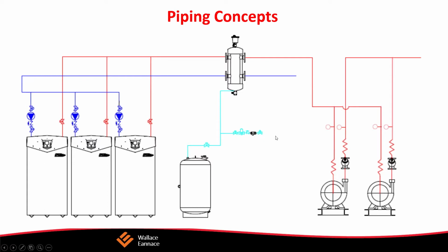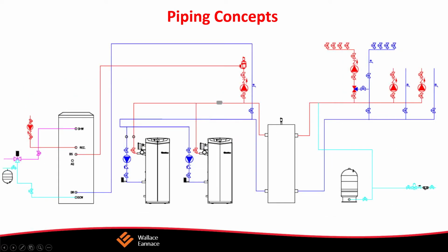Now, that's a recommendation. Using this reverse return piping concept is something that we really recommend if you have multiple boiler applications. You really want to pipe these in this reverse return. The first boiler going out to the system is going to be the last boiler coming back.